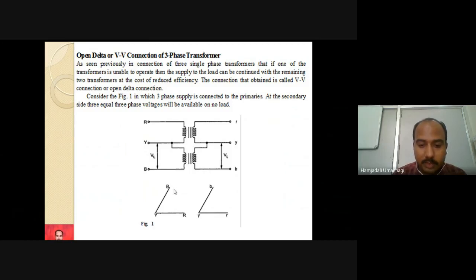And the associated voltage phasor diagrams you can see here. This is R, this is Y, and this is B, and in between there is a gap. The gap indicates the absence of the third phase transformer. Similarly, here also there is a gap. Here also once again the phases are small r, small y, small b. If you check the symmetry of the phasor diagram, the primary phasor diagram is the same as the secondary side phasor diagram. Both are in phase with each other. But here one phase is absent. Because of that, it looks like the English letter V, or it looks like an open delta. For that sake, we call it open delta.